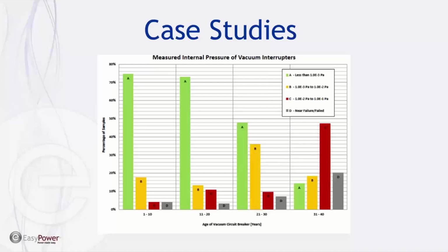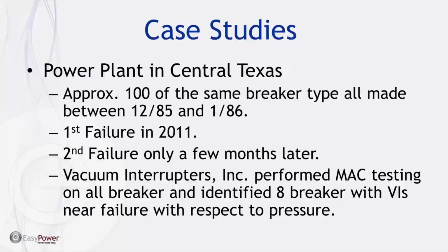And so again, the boom was in the 1980s, so we're well past that 35-year mark, and are seeing these failures now. So another case study was a power plant in Central Texas. They had approximately 100 of the exact same type of circuit breaker, and all of their circuit breakers were manufactured within 1 month of each other, between December of 1985 and January of 1986.